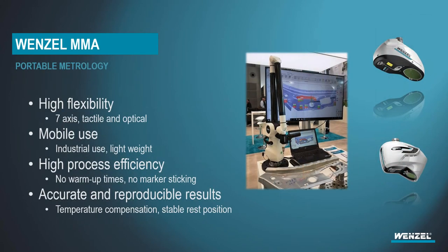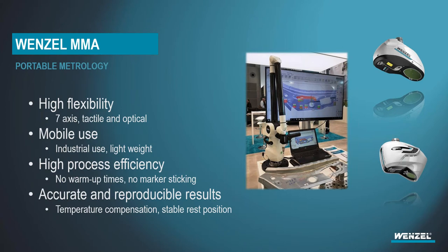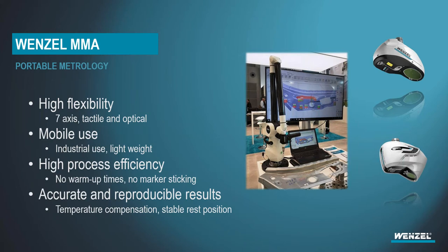Jonah, what is the Wenzel MMA? So the Wenzel MMA is the mobile measuring arm by Wenzel and it's a fully seven axis either tactile or optical sensor portable measuring device. It's obviously mobile. You can have this placed on a magnetic base to take out to your machine tool or out in your shop floor environment. You can also get with a tripod or a rolling cart. So it's movable to different areas of facility, different rooms, different areas of a manufacturing plant, built-in temp comp, built-in Wi-Fi capability, and also built-in battery.